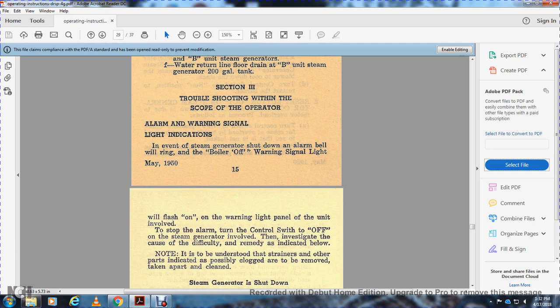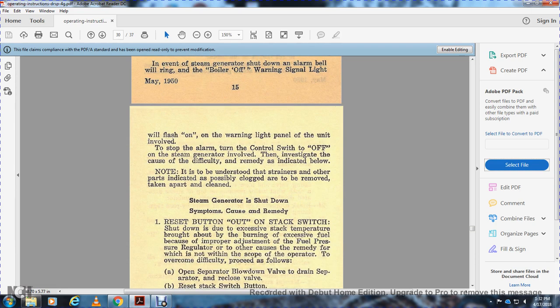If it is understood that the strainers and other parts indicated are possibly clogged, they are to be removed, taken apart and cleaned. Steam generator is shut down - symptoms, cause and remedy: 1. Reset the button on the stack switch.